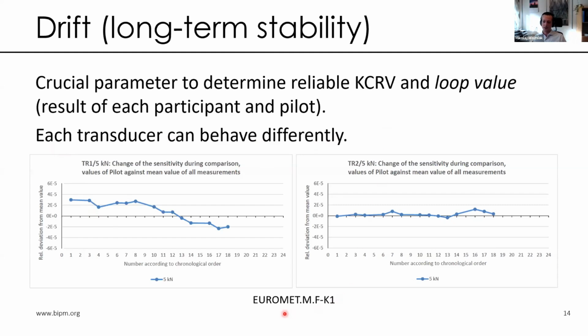I took an example from an RMO type key comparison, key comparison Euromet K1, where in these two graphs you have measurements of two different force transducers at 5 kilonewtons. On the left side you can see that the behavior of this transfer standard shows more or less a linear dependency in time, whereas the other behaved quite stable. You can see that the drift between different measurements is quite low.